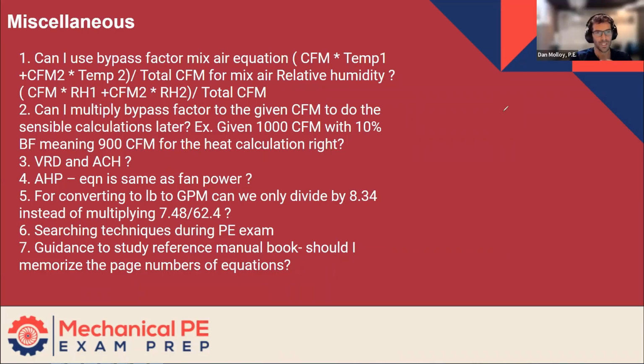Hey, Dan, if I may chime in, I just happened to come across a solution where you specifically talked about this. I recall an example you gave of 10,000 CFM passing through the cooling coil, and I believe the efficiency was 90%. You showed side-by-side calculations where you use the traditional bypass factor formula, derive the efficiency, and then use that efficiency to find the temperature.